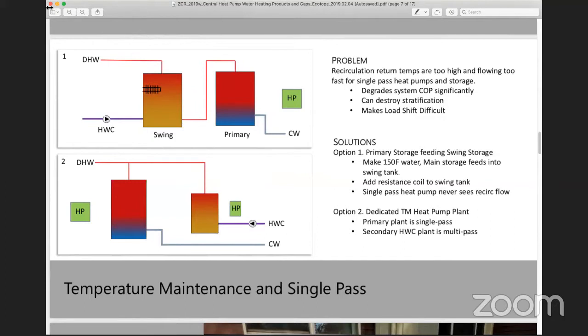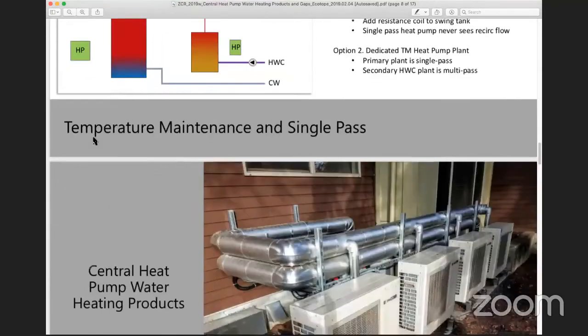And then the second one, usually with bigger buildings, is a dedicated heat plant for the recirc. The recirc comes in and gets its own heat pump, and the cold water, or the primary domestic hot water heating, gets its own heat pump and storage sized accordingly. So these are two solutions, both set up around single pass options, that we've had success with. Next.